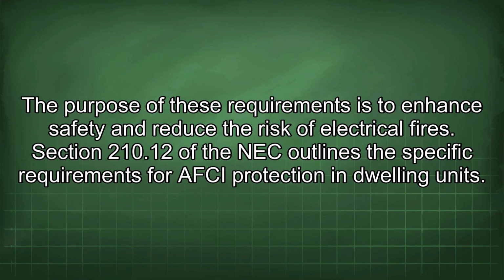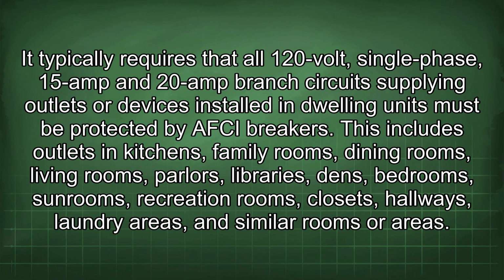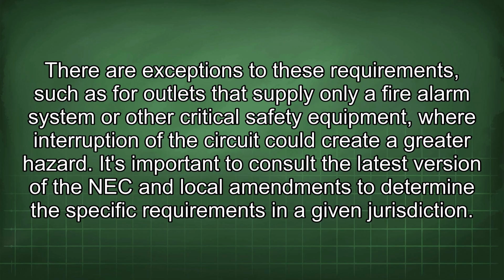Section 210.12 of the NEC outlines the specific requirements for AFCI protection in dwelling units. It typically requires that all 120-volt, single-phase, 15-amp and 20-amp branch circuits supplying outlets or devices installed in dwelling units must be protected by AFCI breakers. This includes outlets in kitchens, family rooms, dining rooms, living rooms, parlors, libraries, dens, bedrooms, sunrooms, recreation rooms, closets, hallways, laundry areas, and similar rooms or areas. There are exceptions to these requirements, such as for outlets that supply only a fire alarm system or other critical safety equipment, where interruption of the circuit could create a greater hazard.